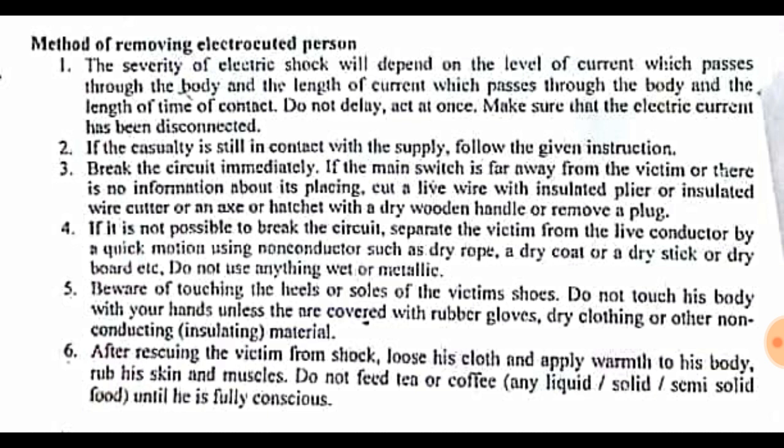If the casualty is still in contact with the supply, follow these instructions. Method one: break the circuit immediately. If the main switch is far away from the victim or its location is unknown, cut the live wire with an insulated wire cutter, an axe, or any wooden insulating material to cut off the main supply.